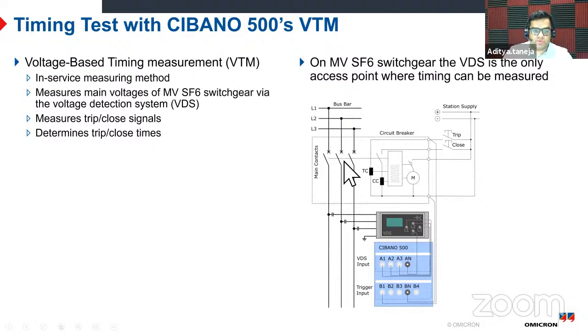Again, for timing measurement, we need to know when the command was given. Since this is online, we don't give a command. We just keep a cable parallel to the command which is coming from the relay, and we trigger our equipment based on that command so that we can start the timing measurement. So again, very useful for such medium voltage GIS, if you happen to see them in future.